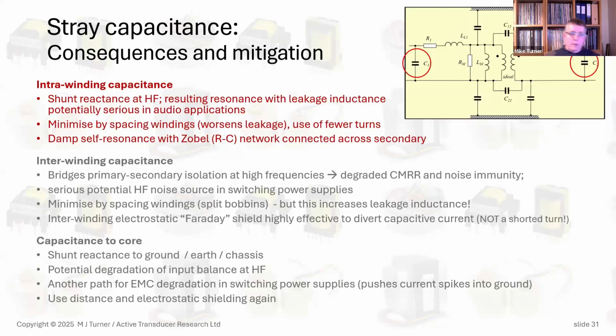How do we minimize that? Well, we use fewer turns on the windings. We can keep the windings apart from one another, keep the turns apart from one another, spacing the windings out. That worsens the leakage inductance, so there's the first compromise. And we can also damp it, as we'll show a bit later on, with loading at the output of the transformer.